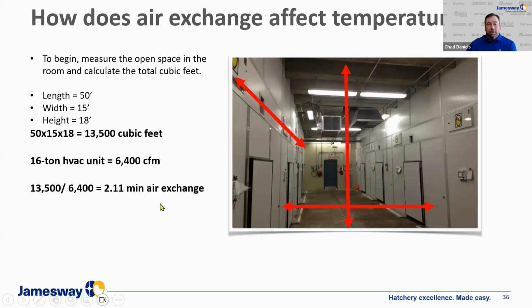What that means is every 2.1 minutes, all the air in that room has either gone through the incubation equipment or has been pulled back up through the rooftop HVAC unit to be reconditioned. And so we can see a unit on the roof that has to cool, or a heat cycle has to function, and it can quickly change the room temperature. In a room with a 2-minute air exchange like this, you may naturally create a temperature variance in the room as much as 8 or 10 degrees, and you can't control it.